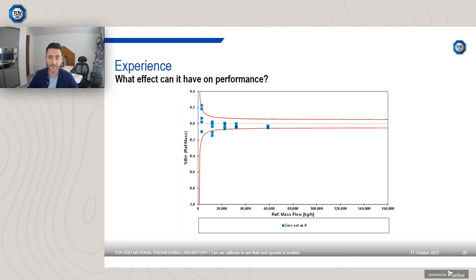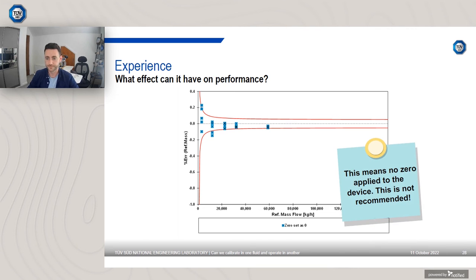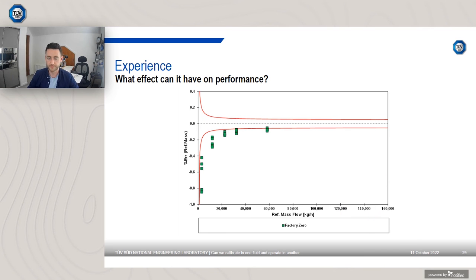Actually looks okay by chance. That's not quite as expected. When I was performing these tests, I was kind of hoping to get larger deviations when I set it to 0, but by chance it looked like this 0 must have been relatively close to being 0. So this means no zero was applied to the device. It's not recommended to do this, I just want to stress that.